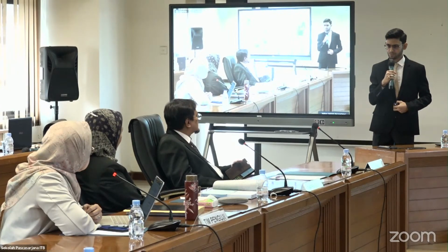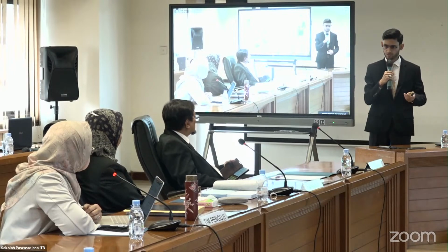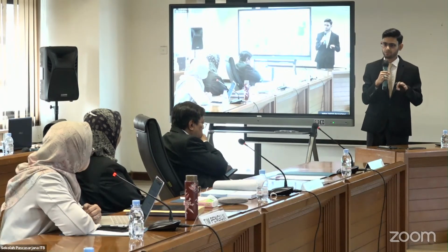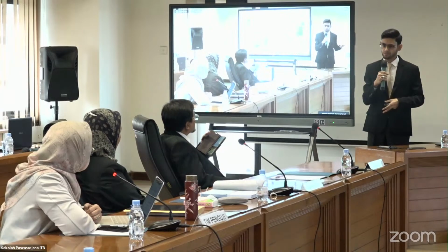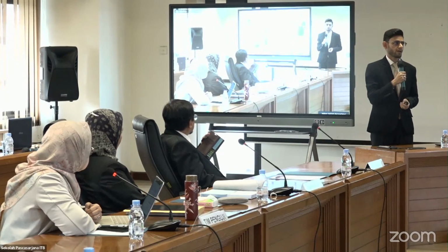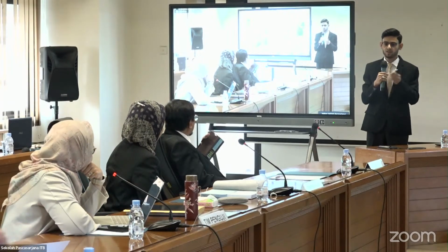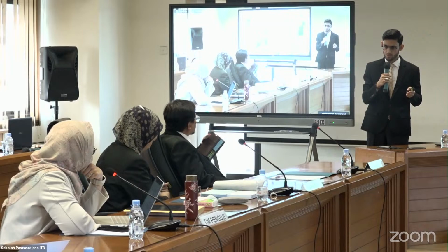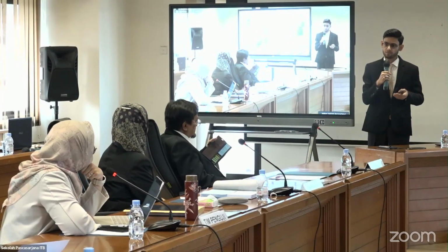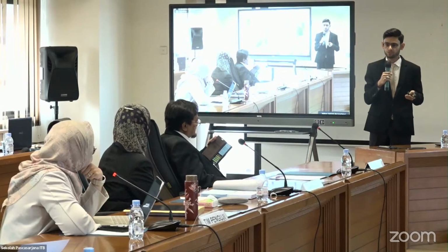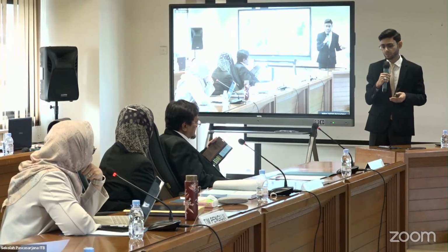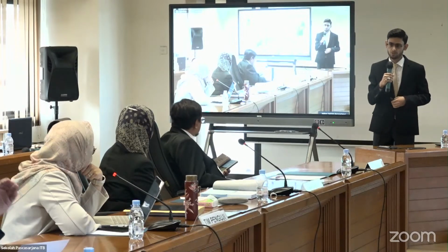It's not based just on the composition of the bacteria. Before starting, we acclimatized our system for a bit with aerobic sludge. Then we start with normal aeration, like 2 liters per minute for 5 minutes on and 5 minutes off, because if we continuously supply oxygen, the operational cost will exceed what is needed. From past research, the DHS column used with another type of anaerobic system could only achieve a maximum of around 75% total decolorization, and sometimes just 45 to 50%. But in our case, we could achieve above 82%, 86% by the end, according to the UV-vis spectroscopic study, and for the COD, we could achieve below the national discharge limit.